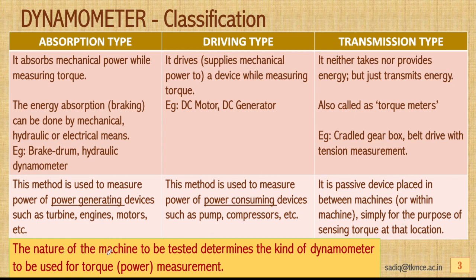From this description we can identify that the nature of the machine to be tested determines the kind of dynamometer to be used. If it is a power-generating device we use an absorption type dynamometer; if it is a power-consuming device then we use a driving type dynamometer.